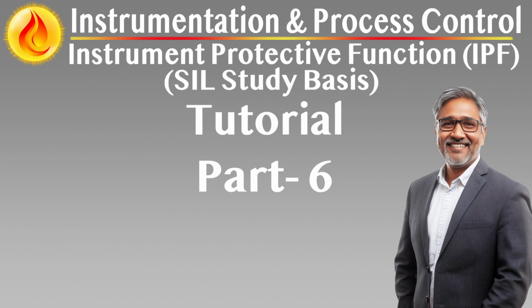The Automatic Maintenance Override Switch, automatic MOS, enabling safe, controlled bypass for routine maintenance activities. The automatic MOS is a purpose-built feature that allows predefined parts of an instrument protective function, IPF, to be temporarily overridden through a controlled, automated mechanism, typically via logic configured within the Safety Instrumented System, SIS.